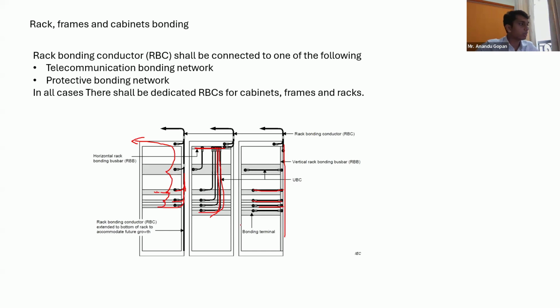Basically, what happens when you loop is, if you have a leakage current or some problem in this place, that leakage current will travel to this place and then to the next, causing issues in other equipment. So you are only supposed to individually earth them, and it must not be looped.